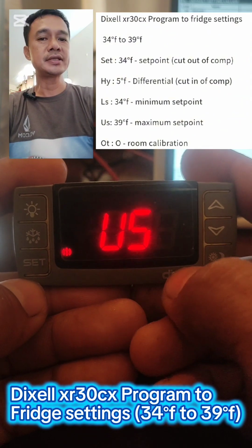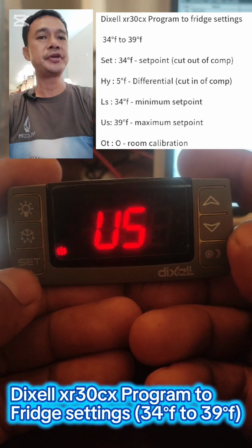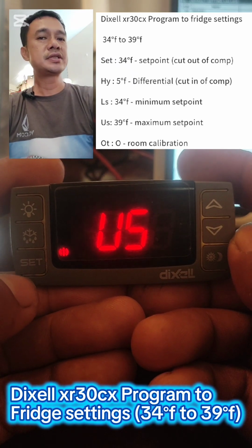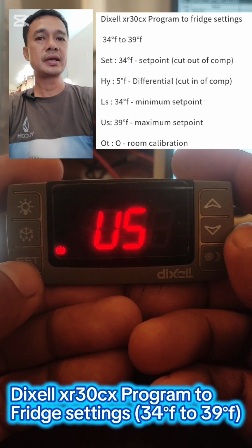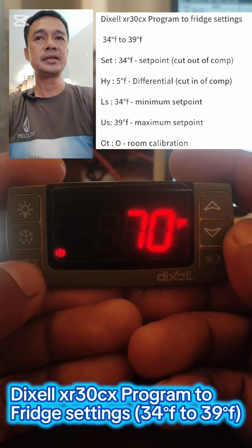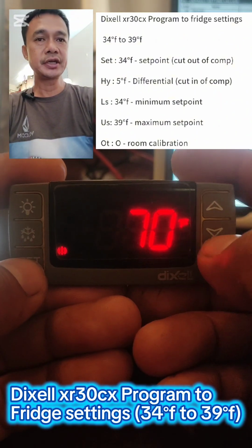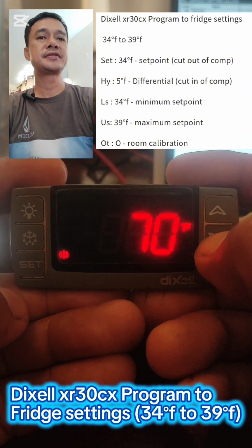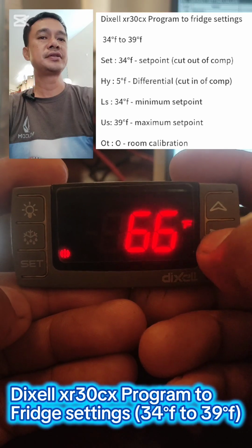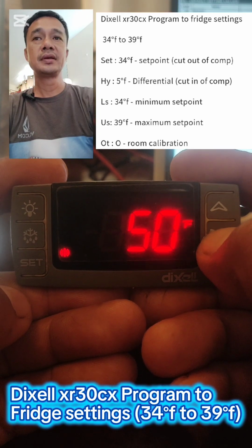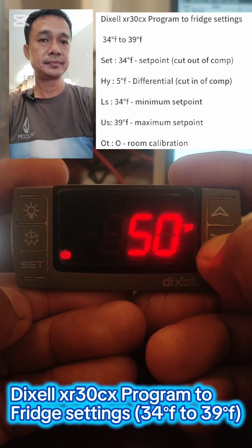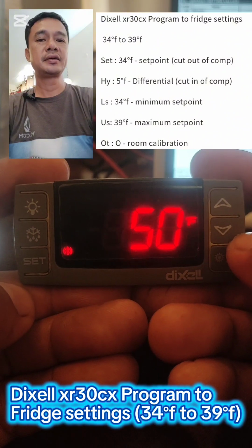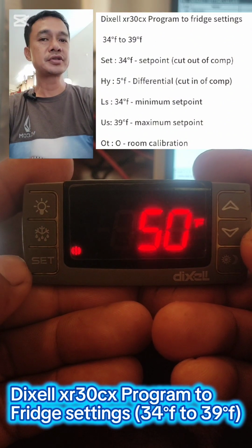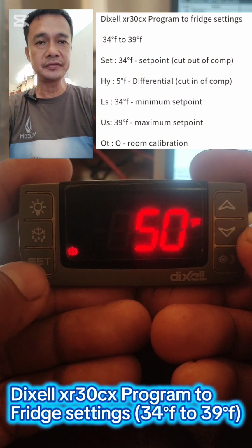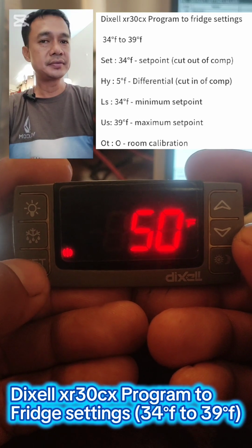And my US, this is the maximum set point, which is the same as my cut-in. And my cut-in is 39 degrees Fahrenheit. So I'm going to change this into 39. Okay, I cannot go further because of the interference of the set point.